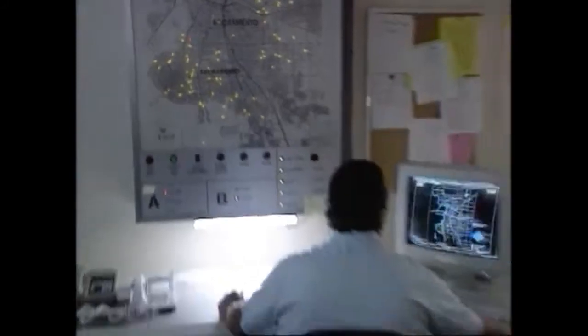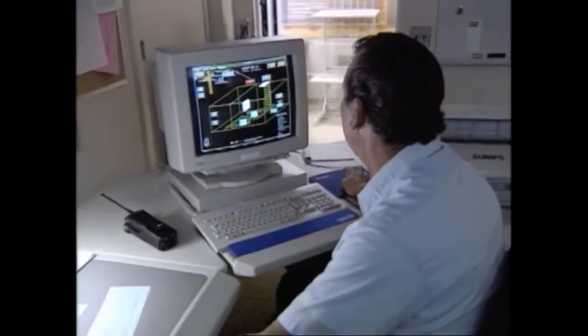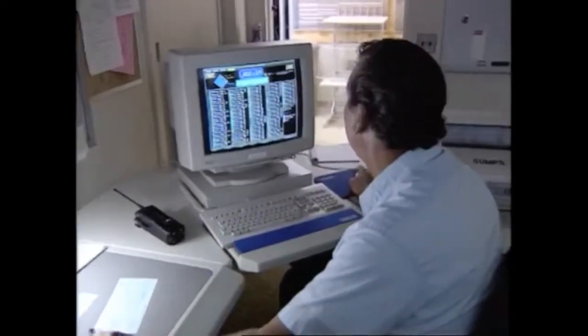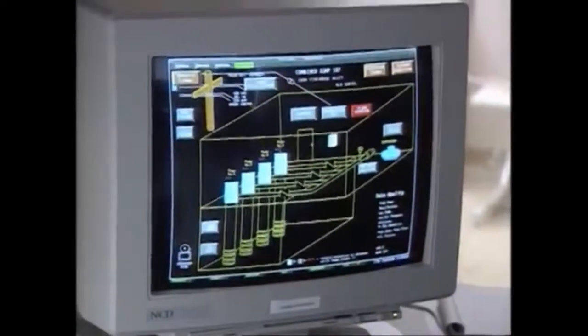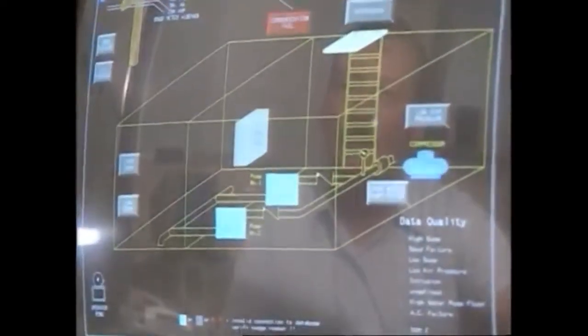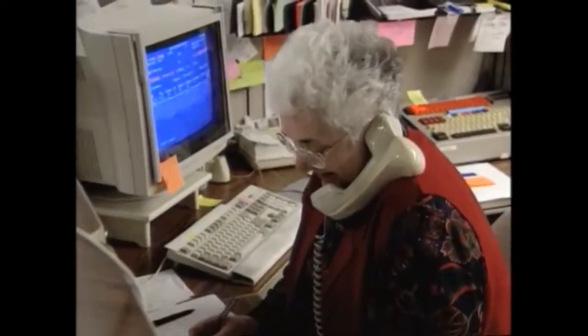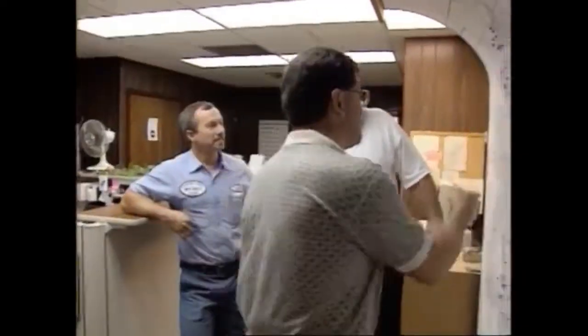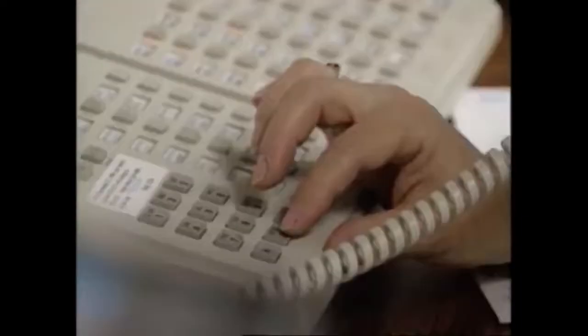With the recent advances in solid-state electronic equipment, telemetered monitoring and supervisory control systems have become much more commonplace in collection systems. These systems utilize an electronic interface device that transmits alarms and monitoring information over radio signals and telephone lines. Information is received at a central location. This could be a dispatch center in the community that's always in service. Examples are the public safety office, or the utility company's dispatcher, if there is one, or a telemetry system that activates a pager directly to a standby person for immediate response.